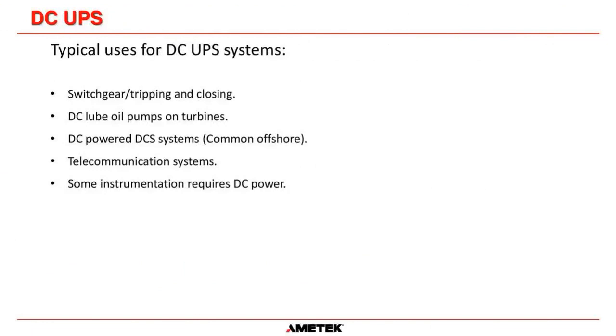Okay, so hopefully that gives you a good overview of the best design of DC systems. Now, what are DC systems typically used for? Most common one is switchgear tripping and closing. Near enough all MCCs in petrochemical industry and at substations have switchgear tripping and closing. We need to be able to trip breakers in an overcurrent situation, even when there is no AC power to supply the tripping and closing mechanisms.